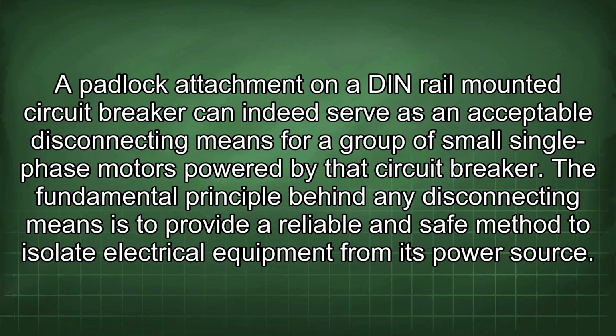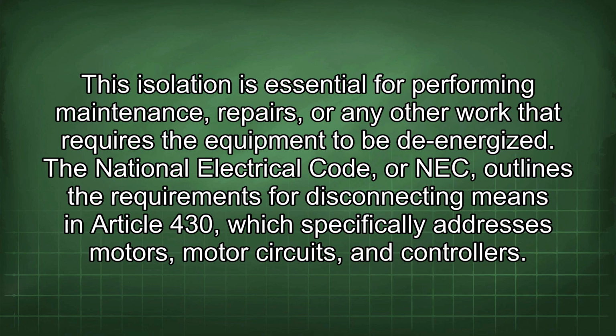A padlock attachment on a DIN rail-mounted circuit breaker can indeed serve as an acceptable disconnecting means for a group of small single-phase motors powered by the circuit breaker. The fundamental principle behind any disconnecting means is to provide a reliable and safe method to isolate electrical equipment from its power source. This isolation is essential for performing maintenance, repairs, or any other work that requires the equipment to be de-energized. The National Electrical Code, or NEC, outlines the requirements for disconnecting means in Article 430, which specifically addresses motors, motor circuits, and controllers.